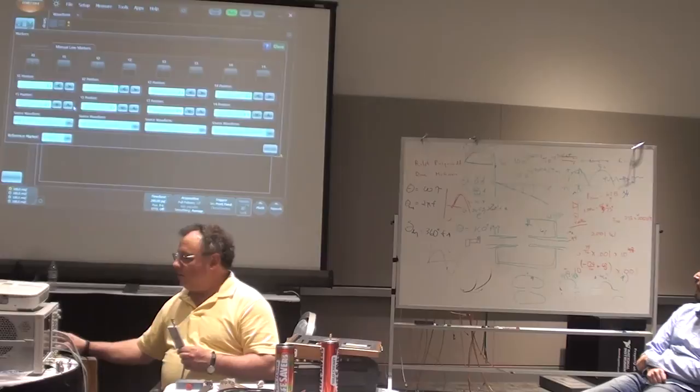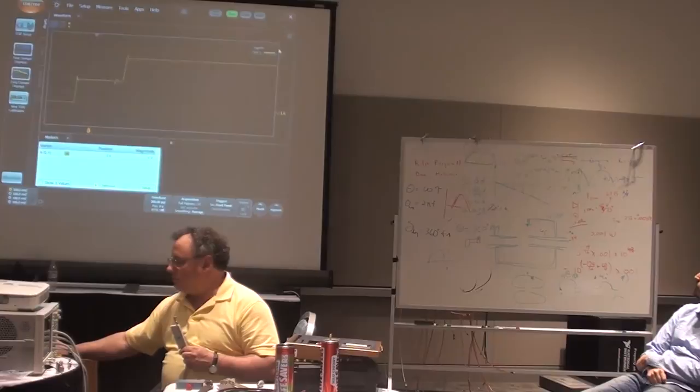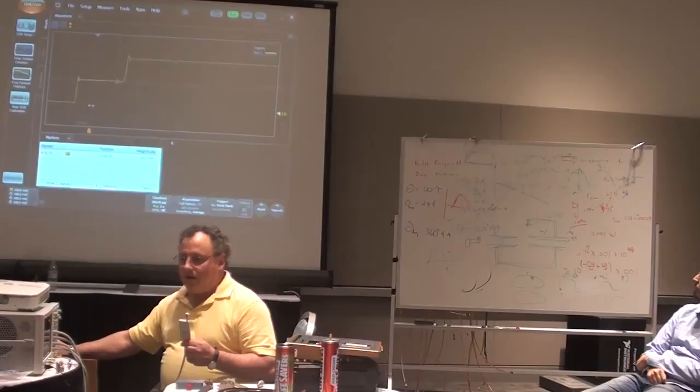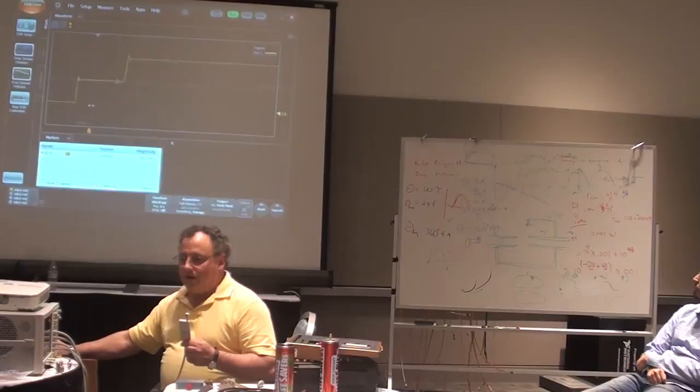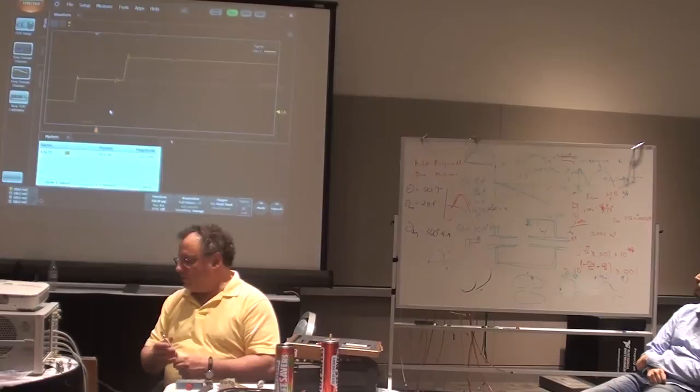So the thing is, it says right there, it says 800 points. And it's 200 picoseconds per division. And you can see 200... That still looks like a straight vertical line. So the pulse starts at some zero volts. Jumps up. It's a 50 ohm system to this point here. And then... Now will it take the markers? Yes. And you can put markers on any of four channels. So we'll just start by putting it right here. And we'll say okay. And all of a sudden here are the markers. Which can I think move either with the knob or with this. And right here you see it looks like minus 144 picoseconds. Because I'm not calibrated yet. And then it appears when the open circuit happens. It's at plus 280. So zero is some place in here. But that's the whole point of calibrating. Is to find out exactly where we want to be.